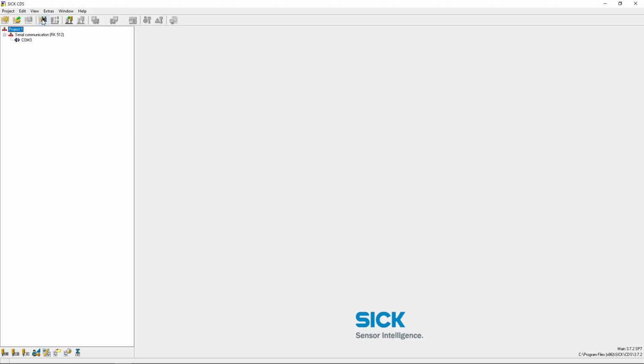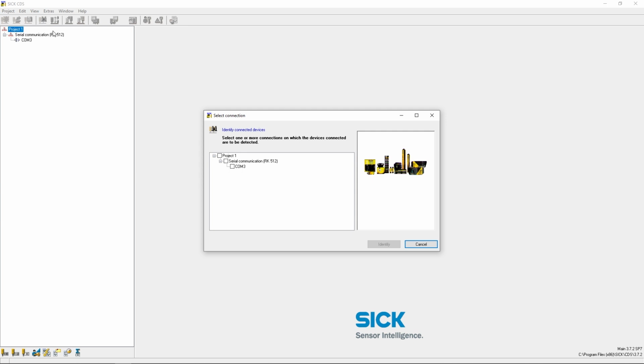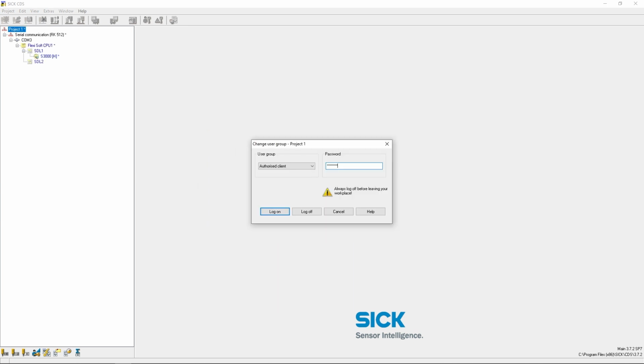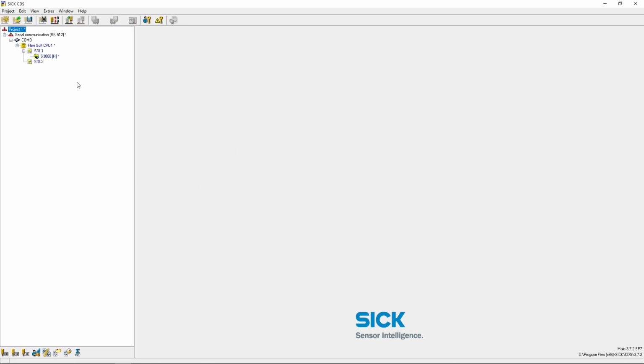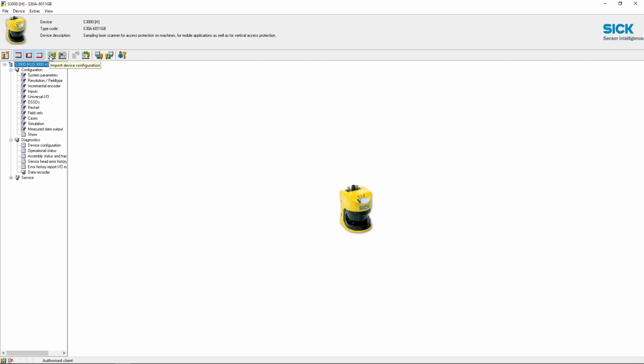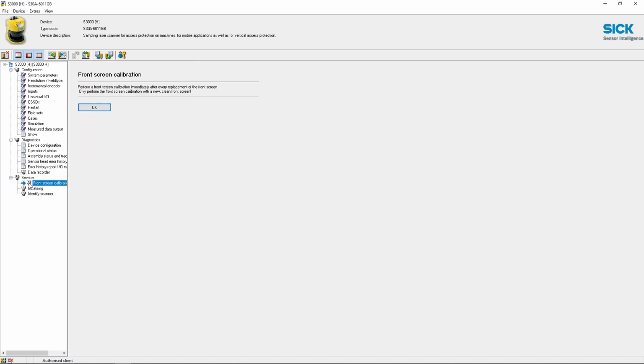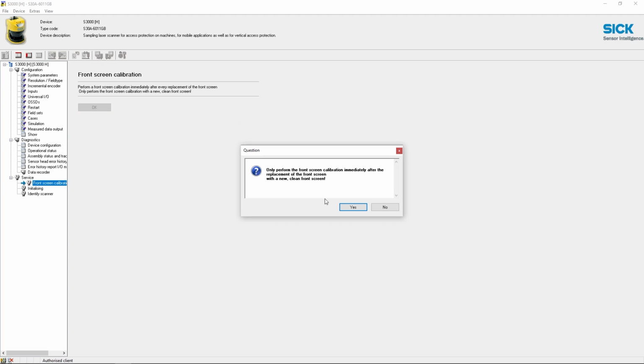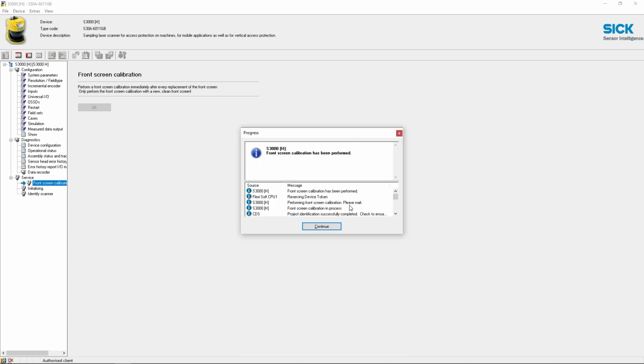To calibrate the optics cover, connect the scanner to a power supply and then the CDS. Identify the project and double-click on the device you want to calibrate. Navigate to the tab Service and then Front Screen Calibration. Follow the steps shown in the software. Afterwards, start the safety function using CDS.